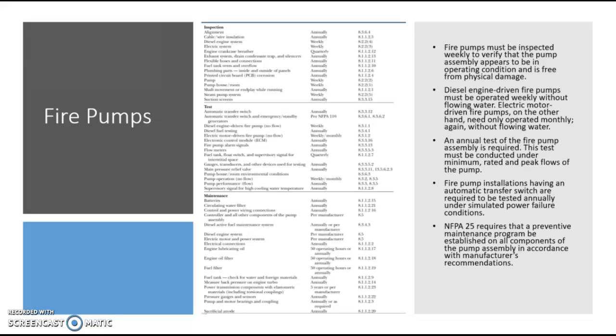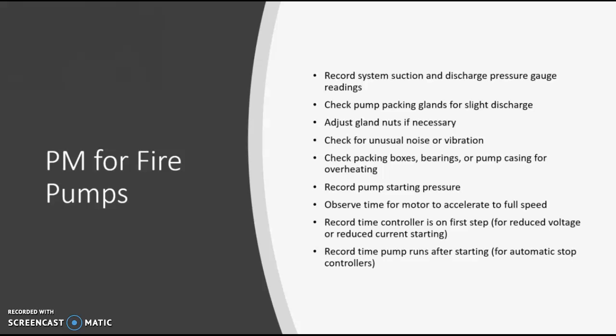And then NFPA 25 requires the preventive maintenance program to be established to make sure that it's all in accordance per the manufacturer's design. PM for the fire pumps. This is all a list of items that we've come up with to tell you what this is. I've gotten this actually from NFPA, but there are several other things you can add to it.